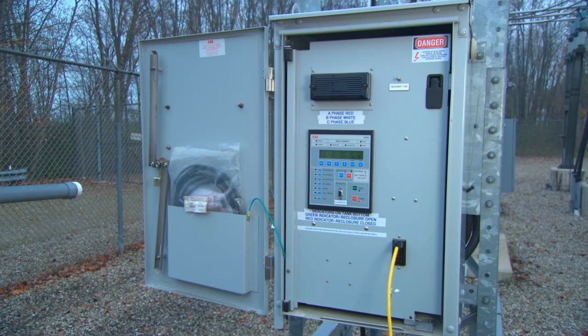The Open indicator would show green beside the Open push button. At the top, you would see a red lockout indicator LED. There would also be an LED status indication beside the phase or ground overcurrent, depending on the nature of the fault. The next visible indicators will be up on the actual recloser.